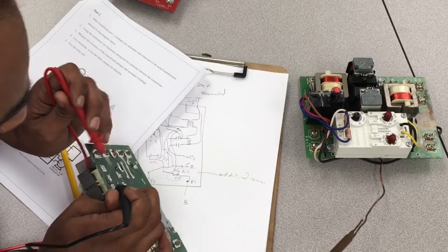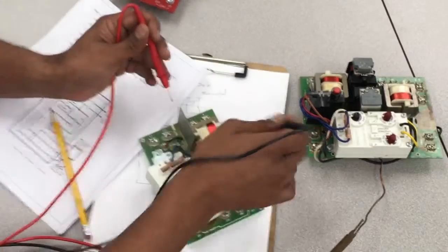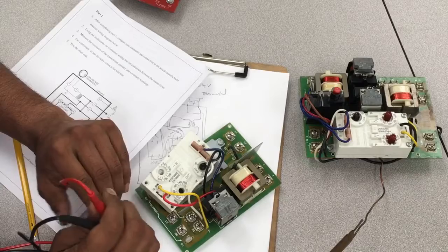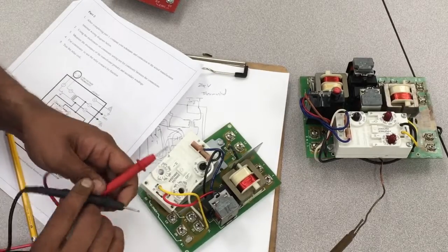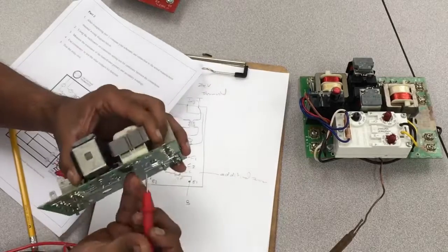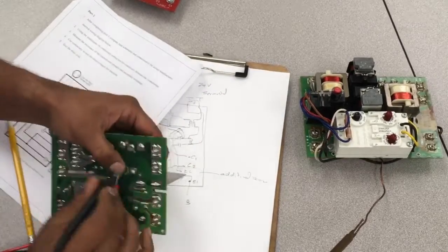I can check the continuity in here, and by checking continuity, you know that this coil is working and we have a solid connection. And then you can measure the resistance of the transformer primary and secondary winding. So I'll put that in resistance, and I'll check the transformer's primary winding, which is here.